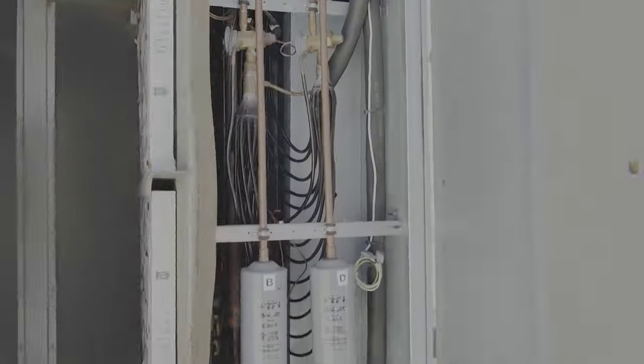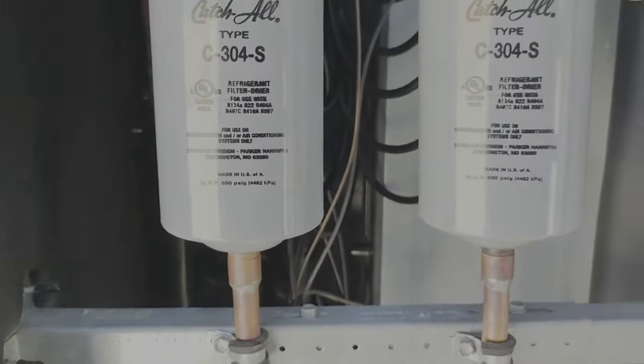So look around in the unit, you know, look for oil. Open all the panels, and it's got some coil right here. We've got some coil, when I look around I see oil there. Let's see if I can make the camera spot it. Right down there, about halfway down. Right over here, all in here there's oil.